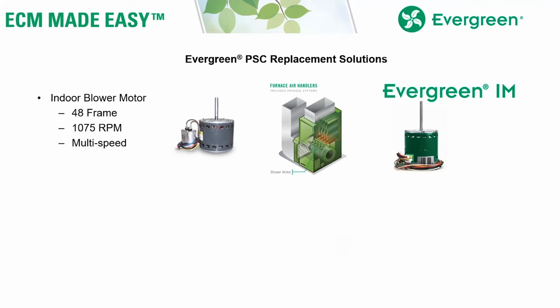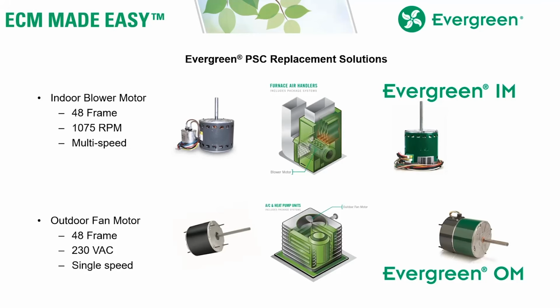Today we talked about the Evergreen IM and its ability to replace multiple ratings of motors with just 2 motors on your truck for replacement of PSC indoor blower motors rated 48 frame, 1075 RPM multi-speed. We also have a counterpart to that motor called the Evergreen OM. It's designed to replace PSC outdoor fan motors, 48 frame, 230 volt, single speed, and it's just as versatile as the Evergreen IM. In fact, one Evergreen OM motor can replace 16 PSC outdoor fan motor ratings all by itself.